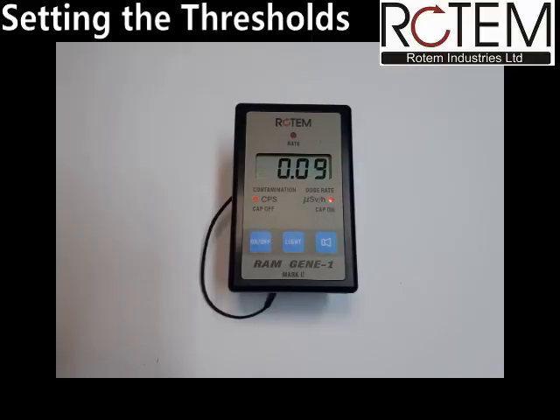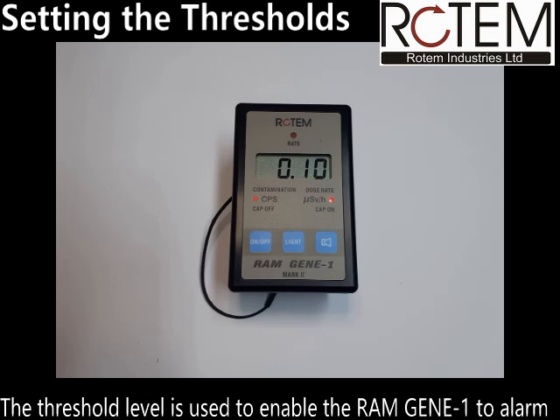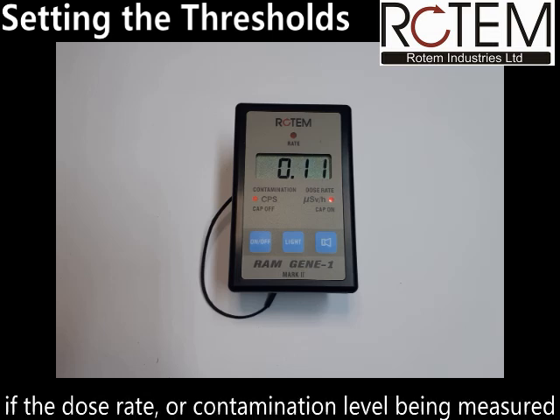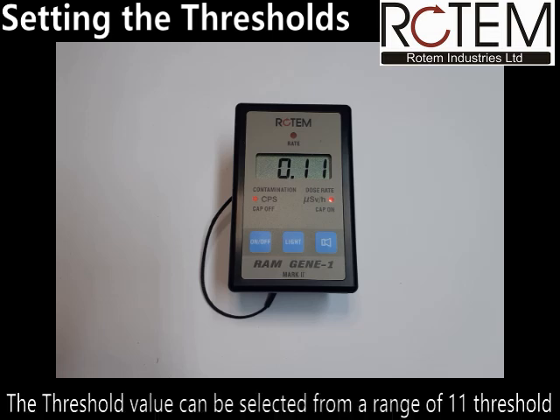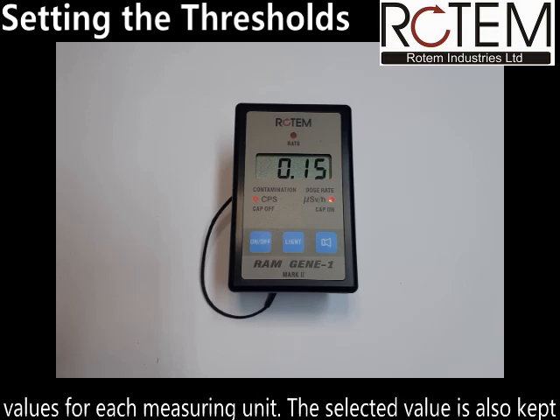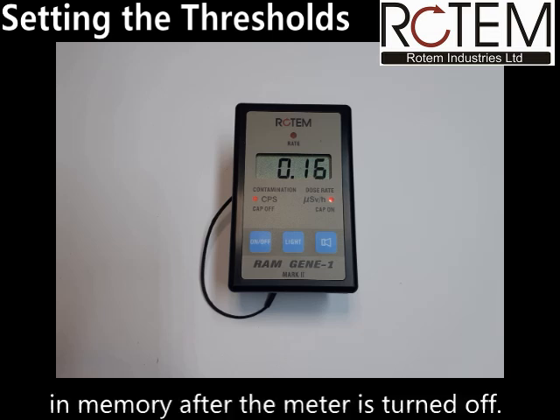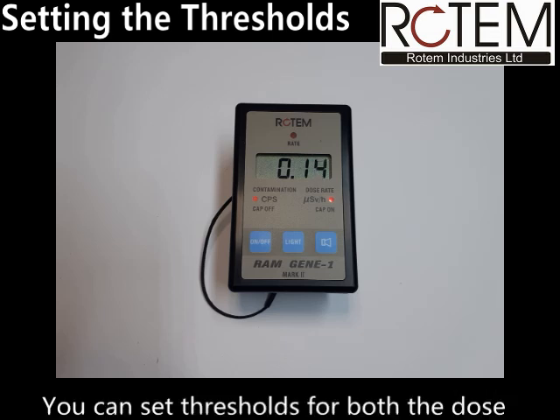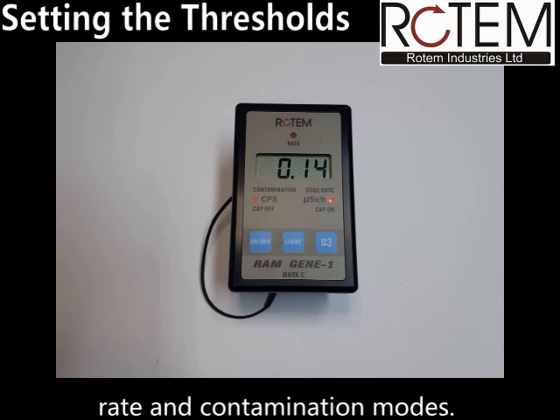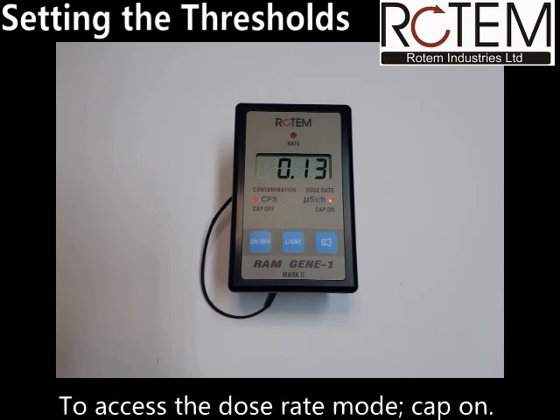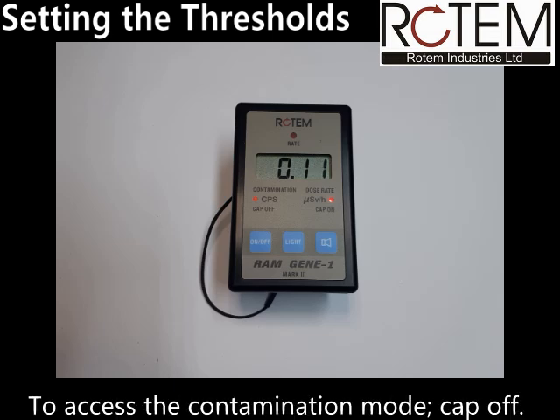Setting the thresholds. The threshold level is used to enable the RAM Gene 1 to alarm if the dose rate or contamination level being measured exceeds the set threshold level. The threshold value can be selected from a range of 11 threshold values for each measuring unit. The selected value is also kept in memory after the meter is turned off. You can set thresholds for both the dose rate and contamination modes. To access the dose rate mode, cap on. To access the contamination mode, cap off.